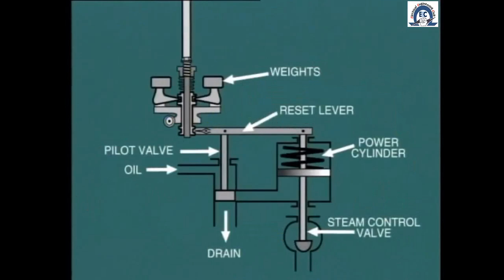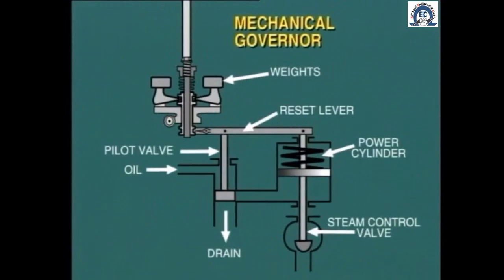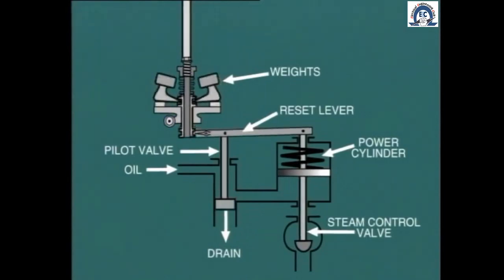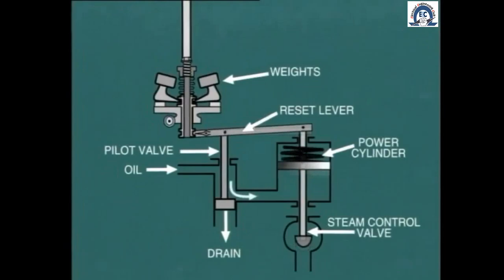This schematic shows us a simplified version of a hydraulic control scheme. In this particular arrangement, a mechanical governor is used to sense turbine speed. A change of turbine speed causes the centrifugal weights to move. For example, a decrease in speed causes the centrifugal weights to move inwards and lower the pilot valve. This in turn allows more high-pressure oil to enter the power cylinder and raise the piston against the compression spring. This movement of the power piston opens the steam control valve and allows more steam to enter the turbine, which causes its speed to increase. Also note, as the power piston rises, the reset lever lifts the pilot valve back into the neutral position again.